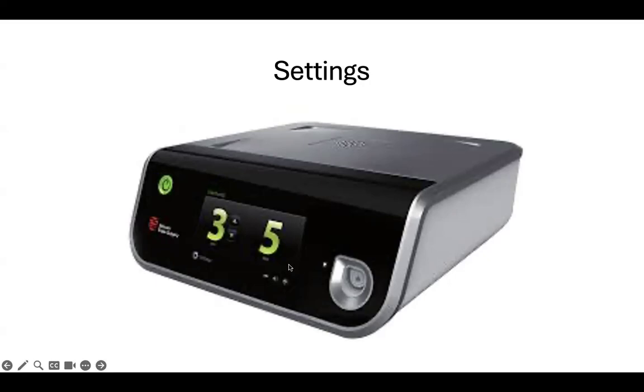So this 3 and the 5 setting just means minimum and maximum setting. Even in your hand control and your foot pedal, you have two separate switches for this. The minimum can go up to 1 also, and the maximum will remain 5. Any setting you want, you can use based on how you want to design it. The difference between the minimum and the maximum setting is just the extent to which the blade is going to rub.